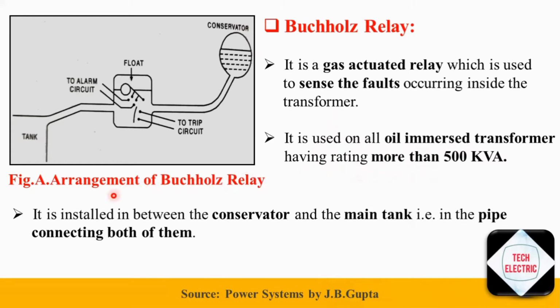Figure A shows arrangement of Buchholz relay. As you can see in the figure, Buchholz relay is installed in between the conservator and the main tank, that is, in the pipe connecting the transformer tank and the conservator. The Buchholz relay consists of two mercury switches, upper mercury switch and lower mercury switch. The upper mercury switch is used to send a signal to the alarm circuit and the lower mercury switch is used to send a trip signal to the circuit breaker.